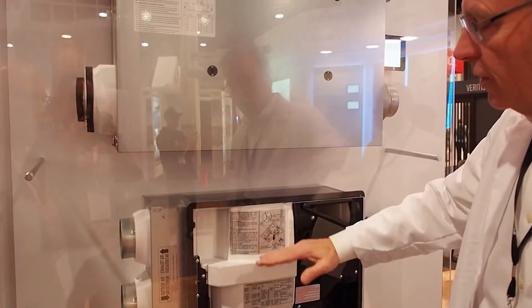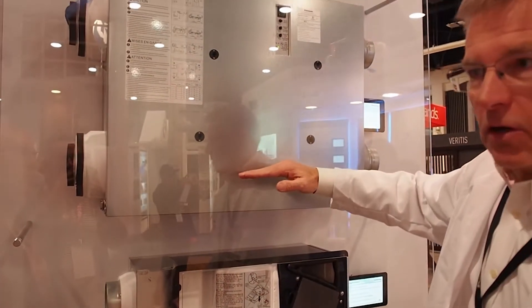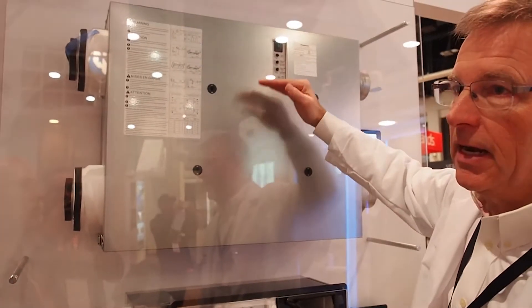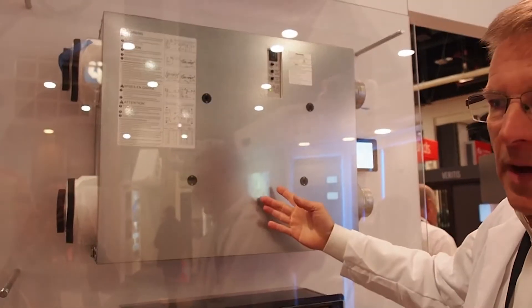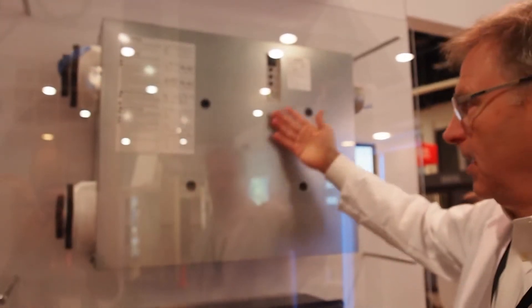The IntelliBalance, I have 10, 20, 30, 40. The IntelliBalance will go 50, 60, 70, 80, 90, and 100. So again, 3,000 square feet is going to require about 90 CFM continuous. I can do that with the IntelliBalance pretty easily.